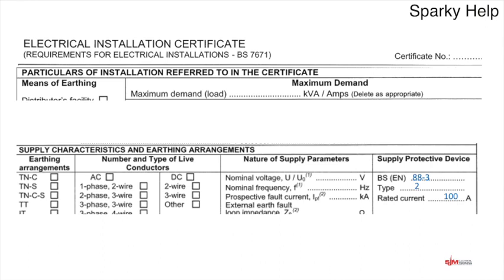Think about it: if you saw a maximum demand of 100 amps on a previous electrical installation certificate, and you wanted to add a new electric vehicle charger with the incoming supply already at 100 amps, trusting that figure would mean there's no more capacity in the system and you'd need a supply upgrade. So you'd probably have to reassess yourself to check whether it is correct.